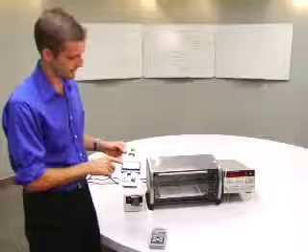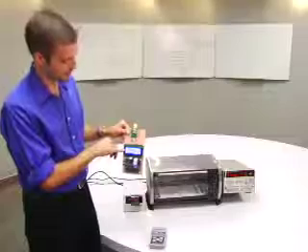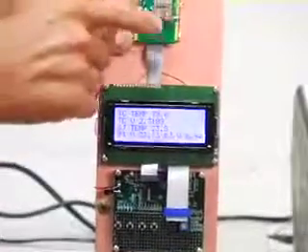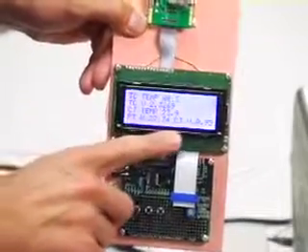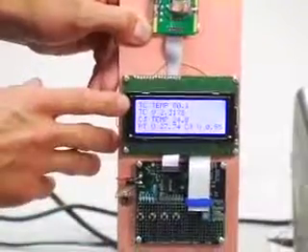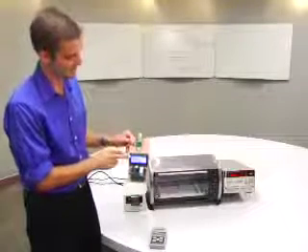Some other information, and this will help with understanding how these meters work a little bit better. We've also got the thermocouple voltage, which at 80 degrees centigrade is about 2.3 millivolts. The cold junction temperature is about 23.8 degrees centigrade, which is the temperature of the internal temperature sensor. The PTAT voltage, or the voltage output from the temperature sensor inside the A to D converter, is about 27 millivolts. And the calculated cold junction voltage is about 0.95 millivolts. And as we saw before, the cold junction voltage at room temperature is about a millivolt. So this voltage is subtracted from the thermocouple voltage and temperature is calculated from that.